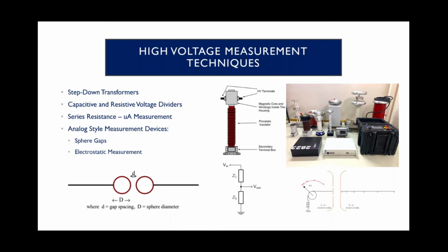You also have some older style techniques, such as sphere gaps and an electrostatic measurement, which are more on the analog side. A sphere gap, you can see the picture down there at the bottom of the slide on the left. Essentially what a sphere gap would do is you have two poles, one that's energized and one that is your low return. And essentially you measure that gap between the two and you move them to a specific point in which a voltage would break down between the two poles. And based on the gap spacing when the breakdown occurs, it's in a controlled environment, you know what the voltage will be. They're not incredibly accurate, but it is a way that some people do make those measurements.